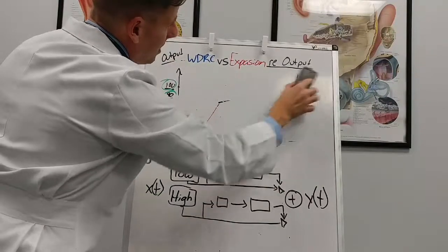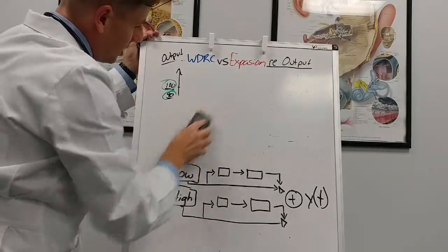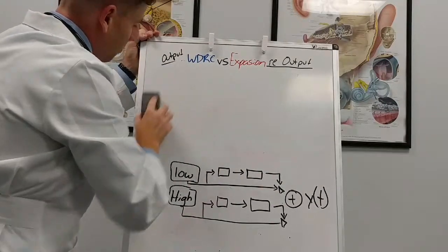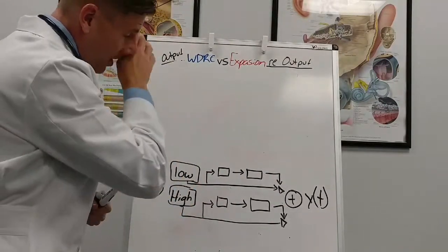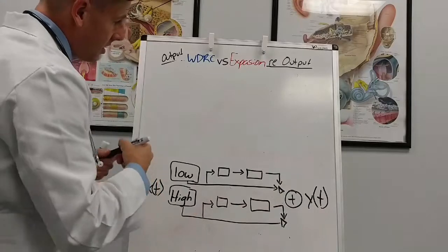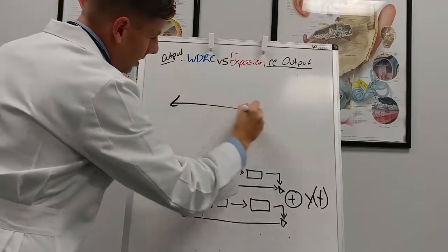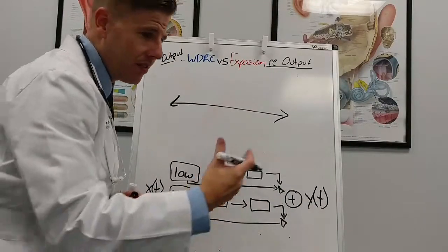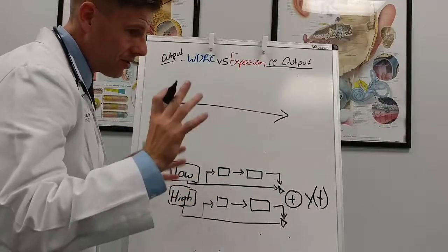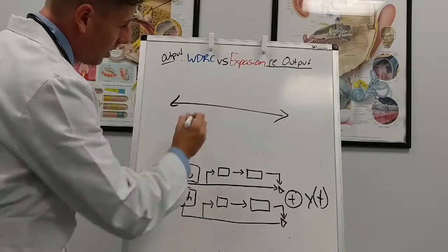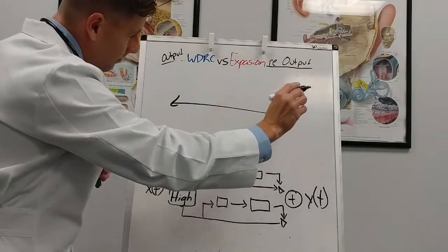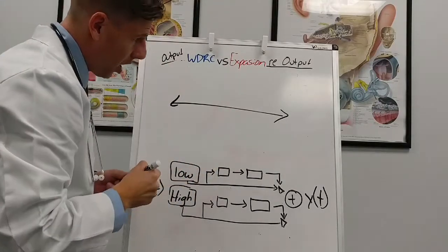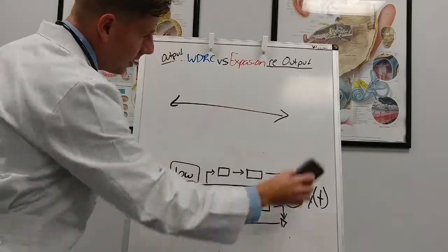So what we talk about here is just the compression ratio really on one frequency or a range of frequencies. And when we first started to go from linear hearing aids to nonlinear hearing aids, we basically did it across the whole frequency range, whatever the hearing aid could cover, 250 to 4,000 or 500 to 6,000, whatever the case was. Our compression scheme was going to take place across the whole board, and that was called broadband compression.